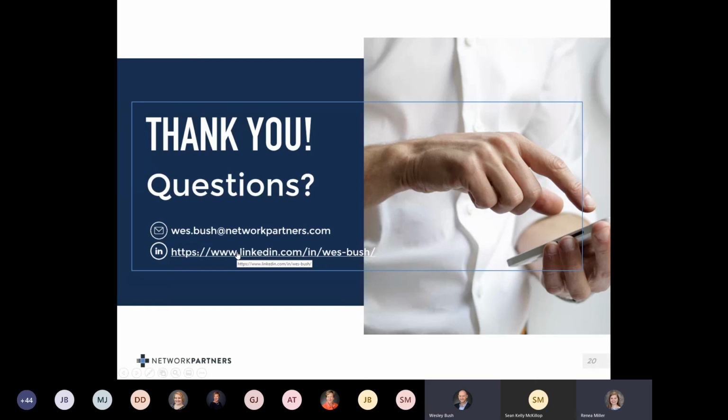First question: in the early design phase, any feedback on how to create a design concept for various sizes of similar devices? Sure. When you're trying to create a package design for multiple devices, the first thing is to understand what's common and what's different. Certainly design initially around what's common, and then potentially create open spaces within the package that allow for the variability in the areas that are not common.